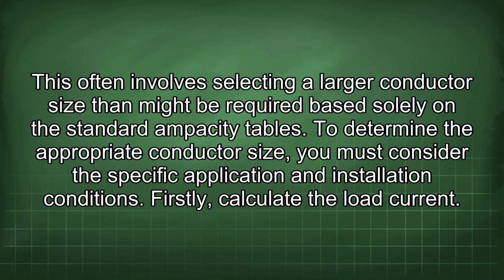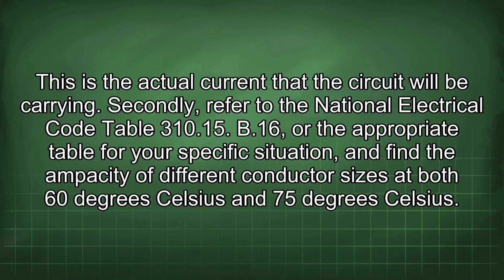To determine the appropriate conductor size, you must consider the specific application and installation conditions. Firstly, calculate the load current. This is the actual current that the circuit will be carrying. Secondly, refer to the National Electrical Code Table 310.15(B)(16), or the appropriate table for your specific situation, and find the ampacity of different conductor sizes at both 60 degrees Celsius and 75 degrees Celsius.